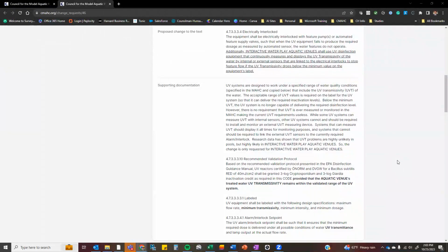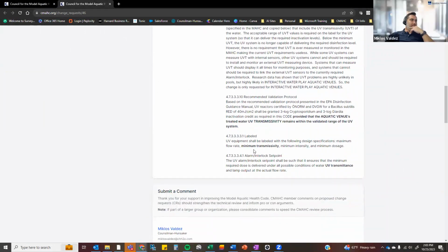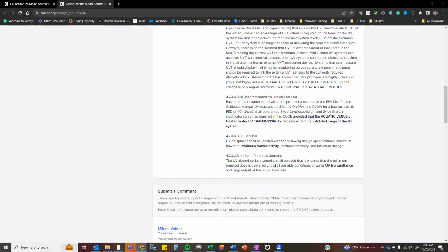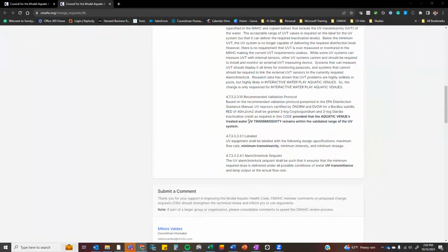This 47334, the top part, not the bottom part. So there's already a standardized sensor that's called out for this equipment. And all this is doing is tying the existing sensor that's already there into the interlock. Not adding an additional sensor, only tying in the existing sensor.